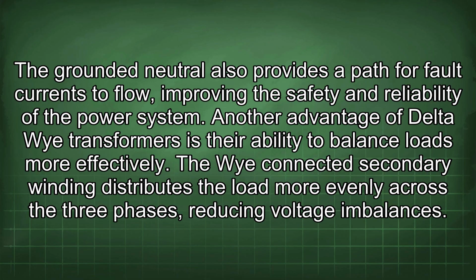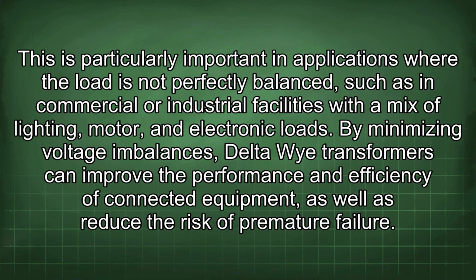Another advantage of Delta Wye transformers is their ability to balance loads more effectively. The Y-connected secondary winding distributes the load more evenly across the three phases, reducing voltage imbalances. This is particularly important in applications where the load is not perfectly balanced, such as in commercial or industrial facilities with a mix of lighting, motor, and electronic loads.